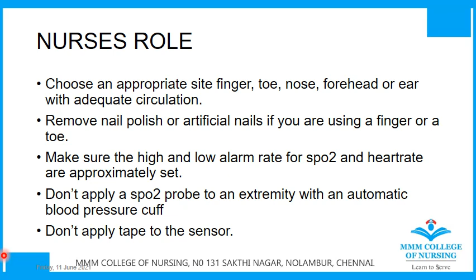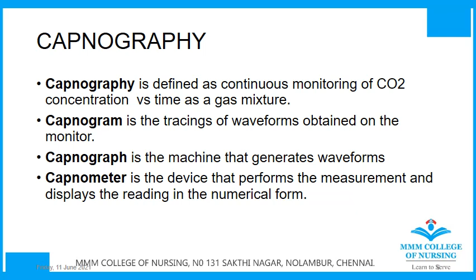Next, capnography. What is capnography? Capnography is defined as the continuous monitoring of carbon dioxide concentration versus time in a gas mixture. Capnogram. Capnogram gives you the tracings of the waveforms which are obtained on the monitor screen. Capnograph. Capnograph is the machine that generates the waveforms. Capnometer. Capnometer is the device that performs the measurement and displays the reading in numerical form. Let's discuss this in detail.